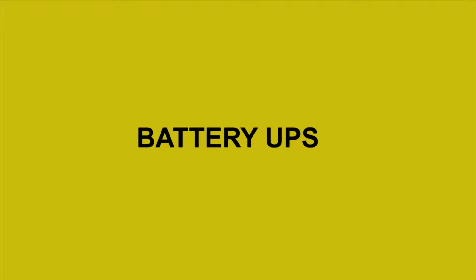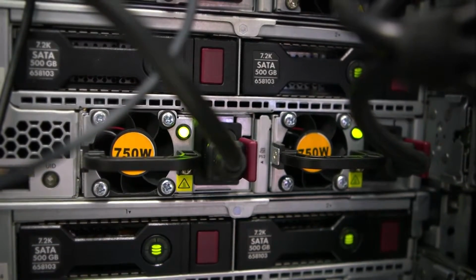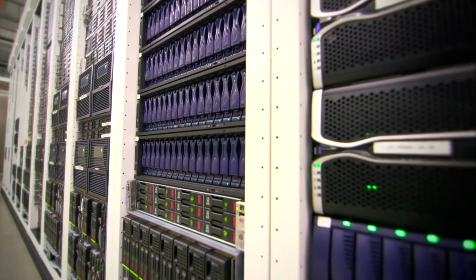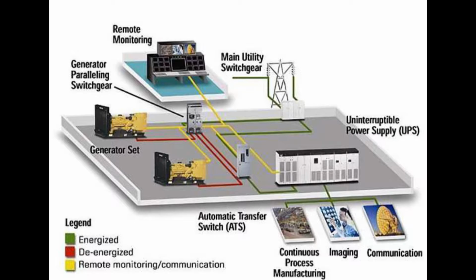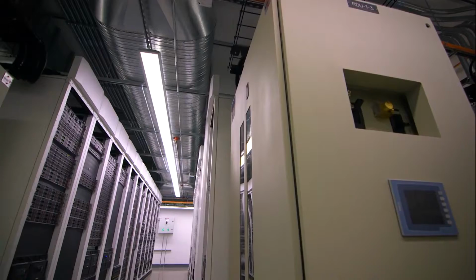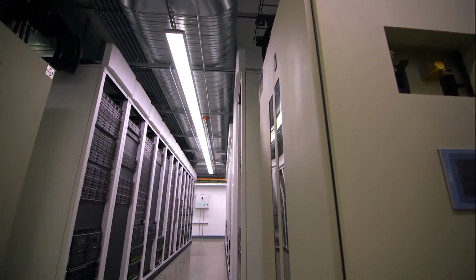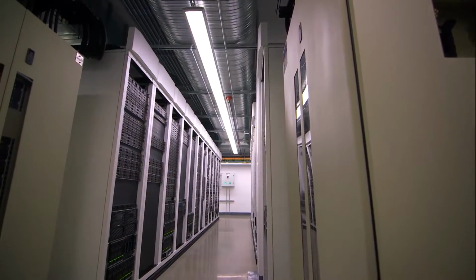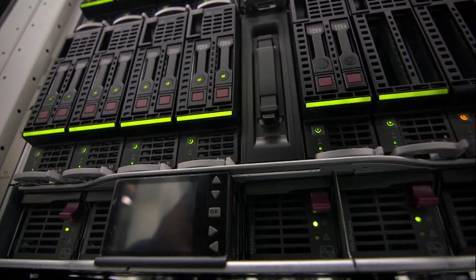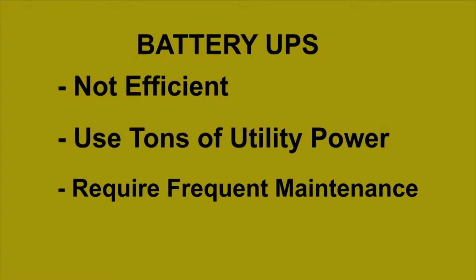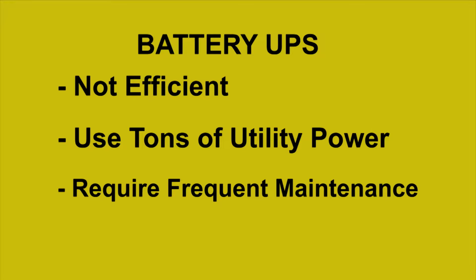There are two types of systems, a flywheel UPS and a battery UPS. The battery system is older technology. On a battery UPS system, AC power comes in from the utility source, converts to DC power through a battery charger. DC power is then stored in batteries until a utility outage occurs. DC power is then supplied by the batteries to an inverter, which converts DC power back to AC. Battery systems are not very efficient to run and use a lot of utility power to maintain the batteries and require a lot of maintenance.